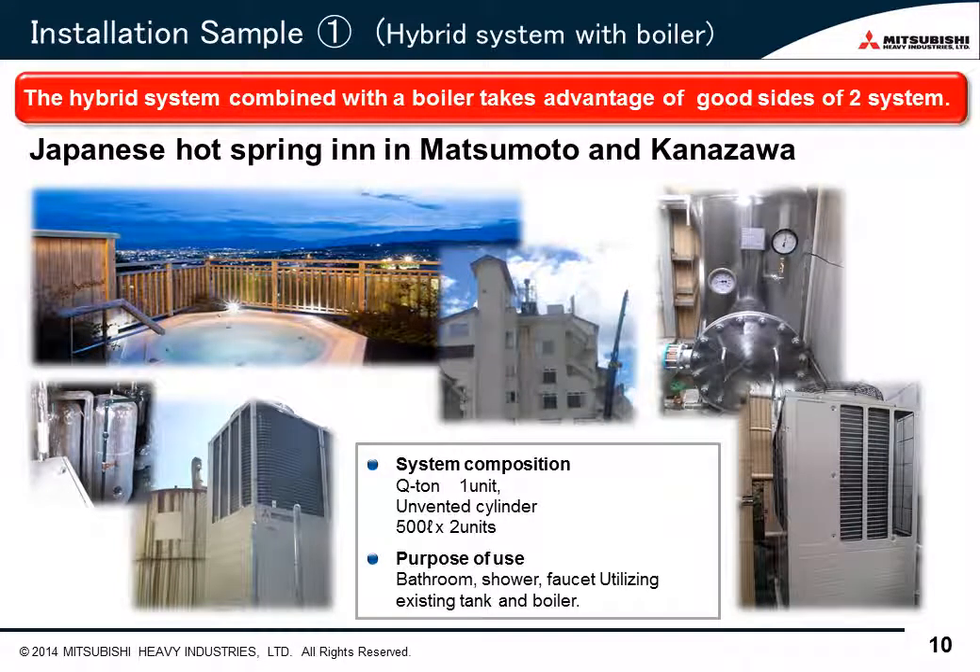Many CO2 water heaters used to be well adopted in welfare nursing facilities or hospitals. Recently, CO2 water heaters have come to be widely used in various fields. First, this is a hybrid system combined with a boiler system. This can reduce initial cost by utilizing the existing boiler and tank. This system takes advantage of each good side of Q-ton and the boiler: the CO2 water heater is used for hot water supply, and the boiler is used for circulation heating such as space heating. Especially in a hotel or hot spring inn, this system has become popular.